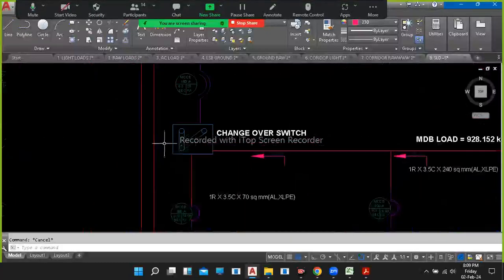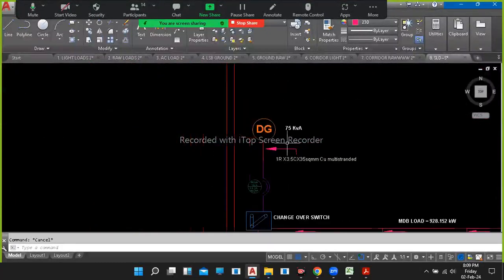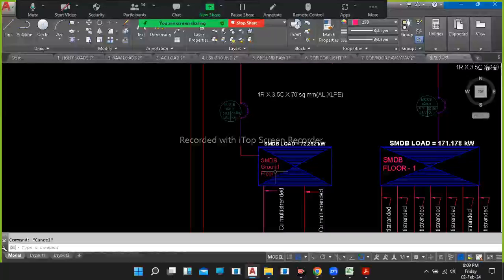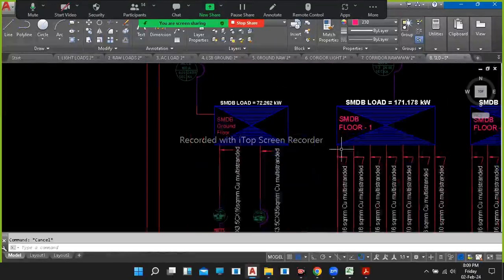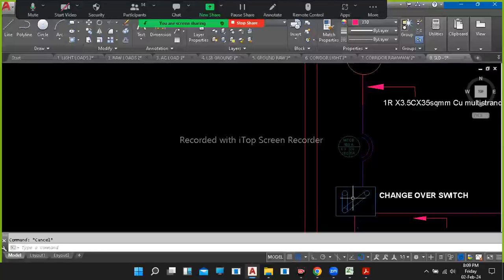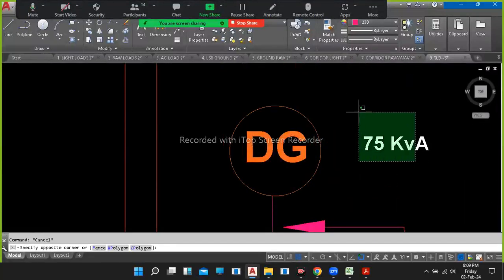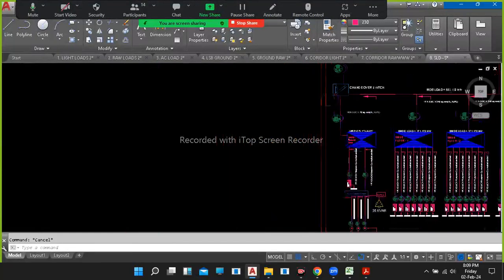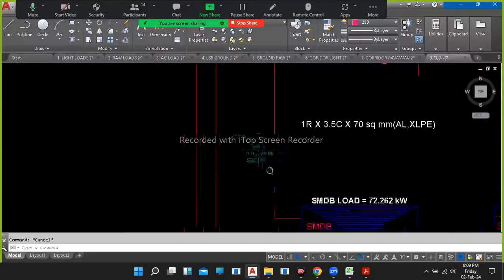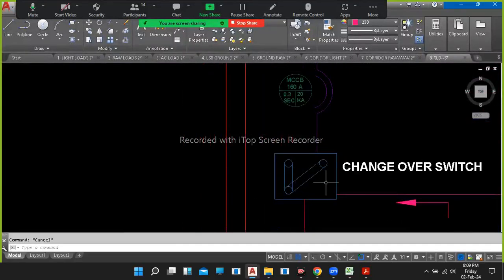Now as per the client requirement, he wants the generator to be provided only for the emergency. So he took SMDB ground floor. Why? Because in every flat we have a UPS. So as per the client requirement, he took the generator sizing and he calculated the generator, he got 75 kVA only for the emergency SMDB ground floor. Based upon 72.262 kilowatt, he calculated the changeover, then he put a changeover.